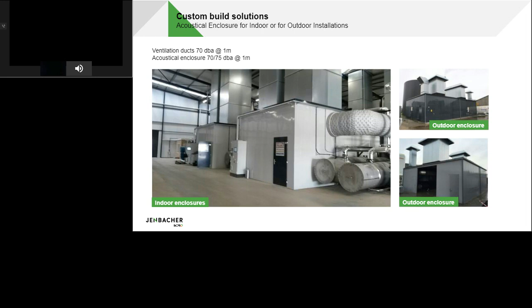Now we're going to look at some drawings of these. On the left, we show the indoor enclosures, with the top view showing the plan view—two generators side by side within the same room. The exhaust systems come off the engines, go down the center, and then into exhaust cleaning, silencers, and any oxidation catalyst or SCRs as necessary. The CO2 offtake is there too, and ultimately there's a vertical stack for the exhaust system to emit gases into the atmosphere.